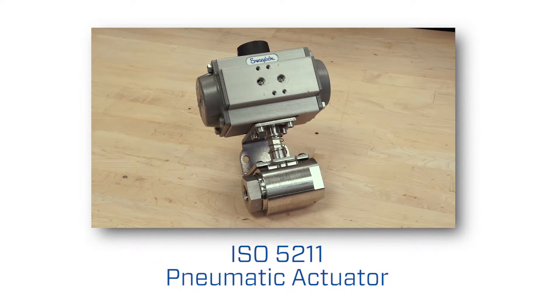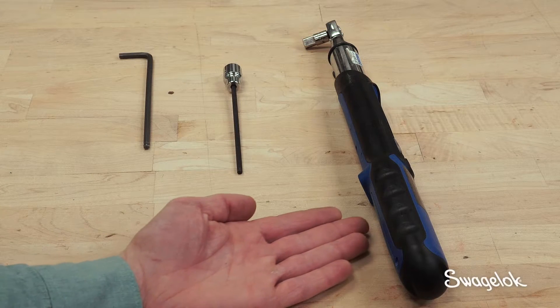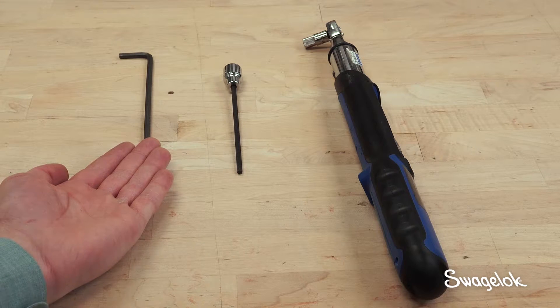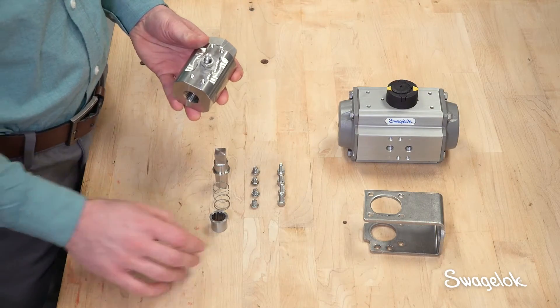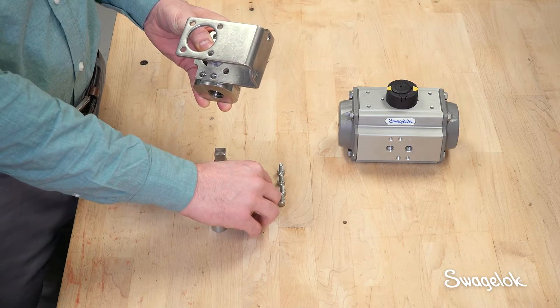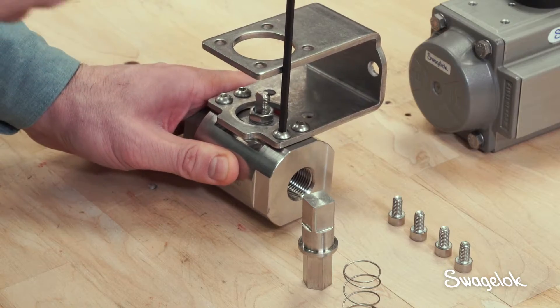Let's walk through how to add on an ISO 5211 pneumatic actuator on a standard ball valve assembly. You will need a torque wrench, a 3/16th inch hex key, a 5 mm hex key, and a 9/16th inch open end wrench. First, insert the mounting bracket over the valve stem and attach the valve body using the four cap screws, torquing the screws to 75 inch pounds.